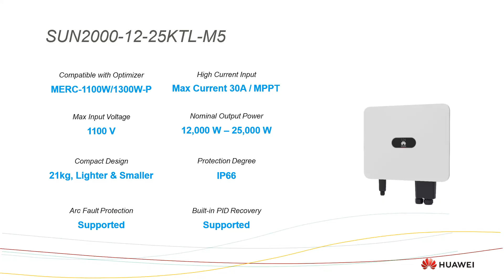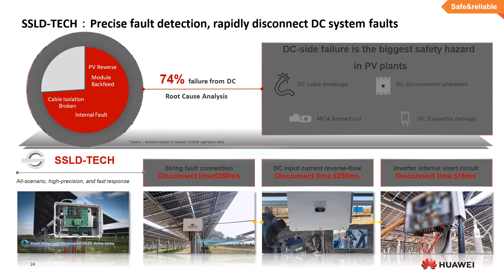Yeah, when we talk about faults in solar systems, based on observations and the different tests, 74% of faults can be considered from the DC side. These faults may include DC cable breakage, MC4 burnt out, or a DC connector fault. So the smart string level disconnector feature is very important in the inverter, and it disconnects the faulty string with a disconnection time of less than 250 milliseconds.